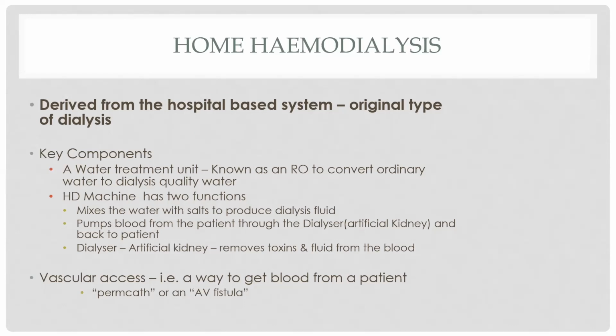There's key components. You need a water treatment unit known as an RO to convert ordinary water to ultra pure dialysis quality water. That machine will reject about 80% of the water coming into it to produce 20% ultra pure water. The machine itself has two functions. It mixes the water with salts to produce your dialysis fluid, and then it pumps blood from the patient through the dialyzer, the artificial kidney, and back to the patient.